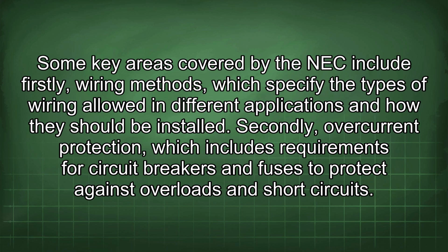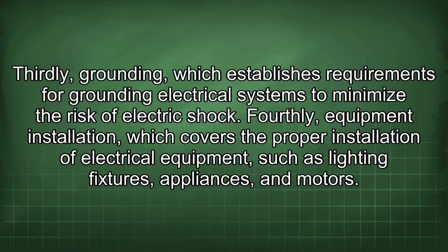Some key areas covered by the NEC include, firstly, wiring methods, which specify the types of wiring allowed in different applications and how they should be installed. Secondly, overcurrent protection, which includes requirements for circuit breakers and fuses to protect against overloads and short circuits. Thirdly, grounding, which establishes requirements for grounding electrical systems to minimize the risk of electric shock. Fourthly, equipment installation, which covers the proper installation of electrical equipment such as lighting fixtures, appliances, and motors.